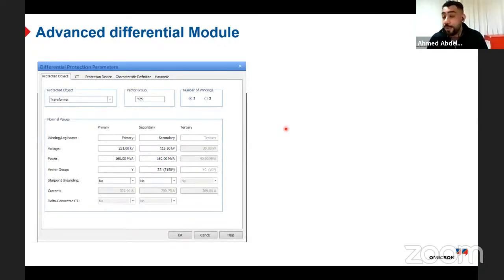I'm entering the data of my transformer. I'm entering the rated voltage of 231, the secondary of 115, then the rated megavolt ampere. Then I'm entering the vector group. Then I'm deciding which group the star point is grounded or not. And also I can have up to a 3 winding transformer, which is a common transformer, by the way. So I can say 3 winding, which maybe YD1, D11, YY0, D5, based on your application. So you can define here any kind of vector group, any kind of connection diagram.